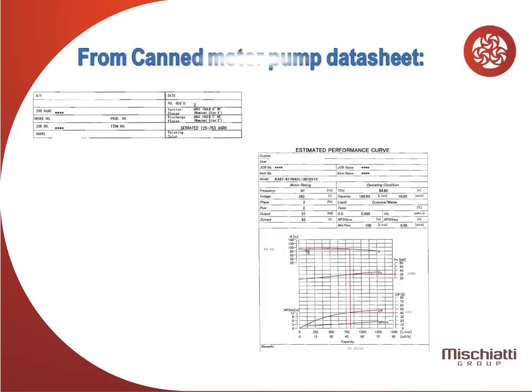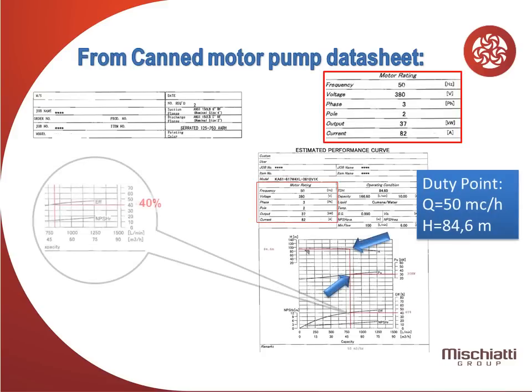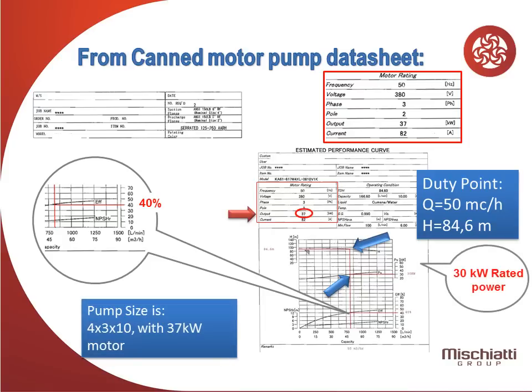From Canned motor pump datasheet, hydraulic efficiency read on curve is about 40%. Selected pump size is 4 by 3 by 10 with a 37 kilowatts motor.